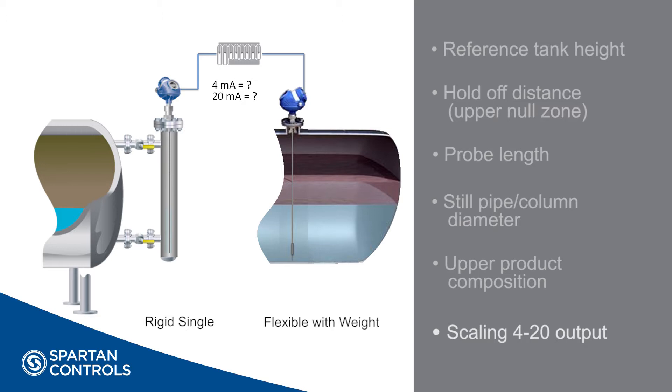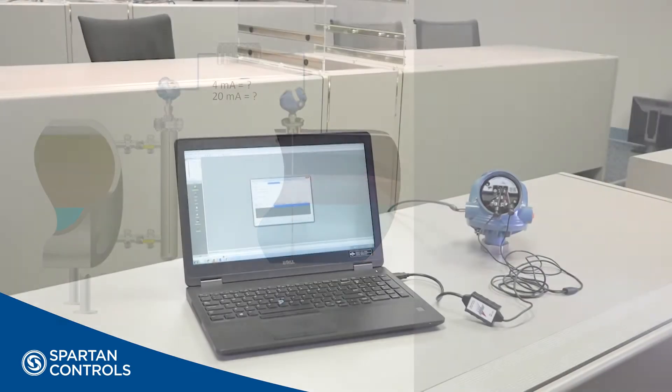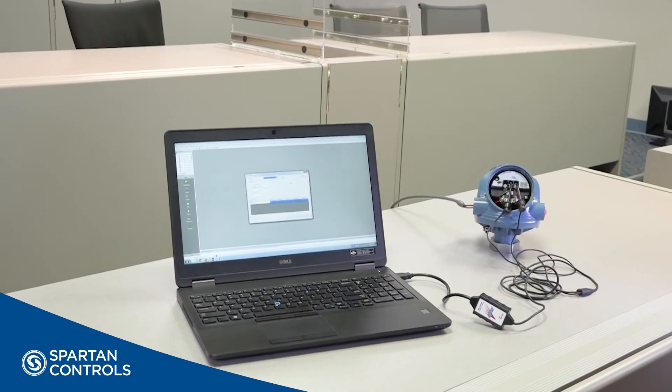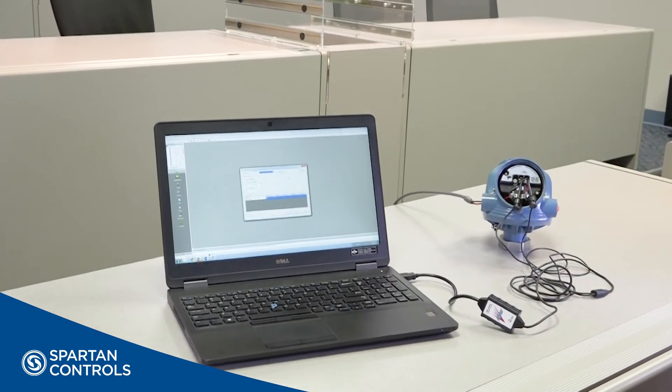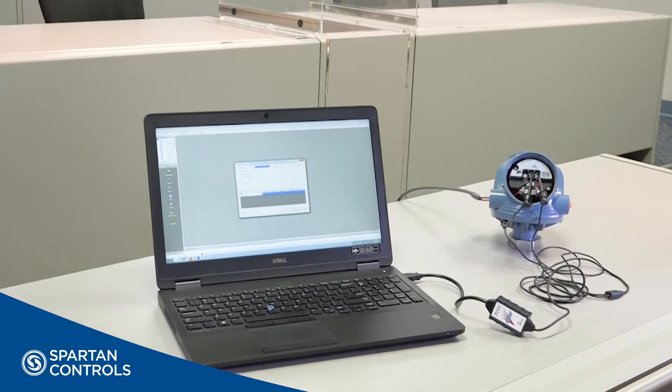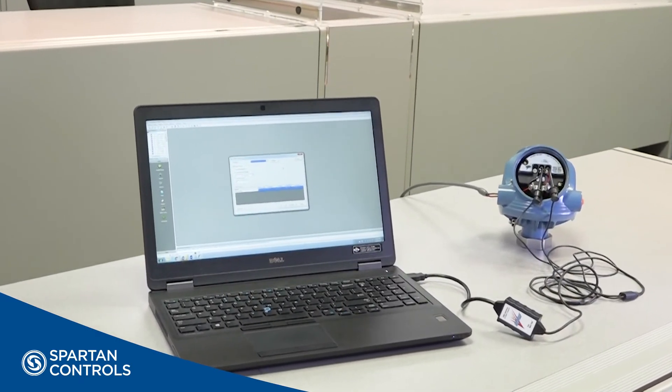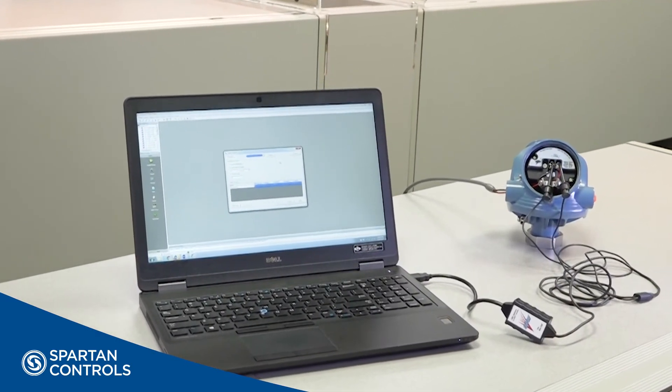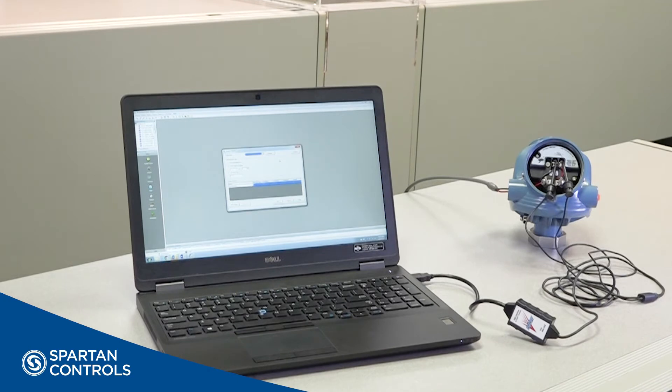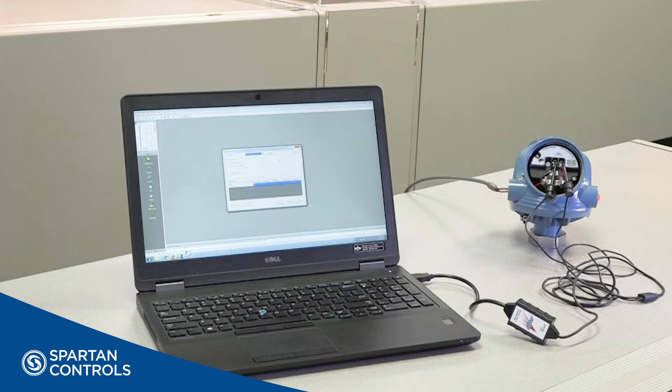If you are unsure on these, it would be best to talk to the operations staff or the programmer that looks after the host PLC, DCS, or RTU on-site. While the 5300 series radar can be configured with a HART communicator, the Rosemount RadarMaster software offers a far superior interface and added diagnostics. RadarMaster is a free software available on the Emerson website; we've included a link in the video description.